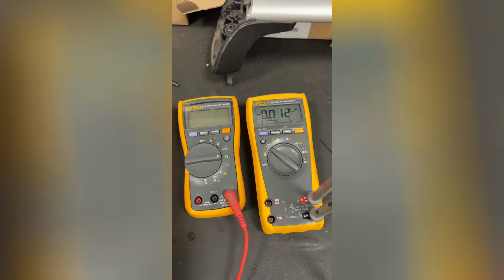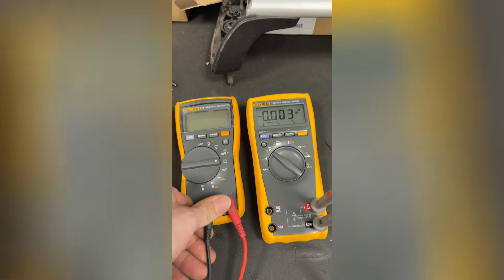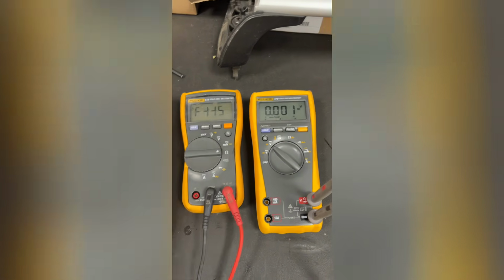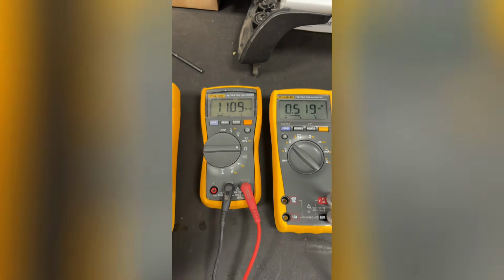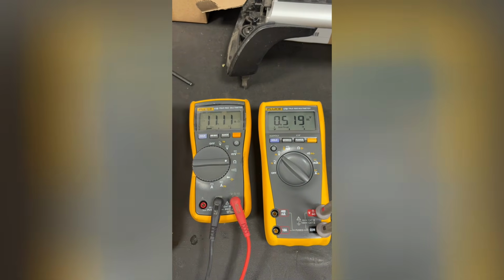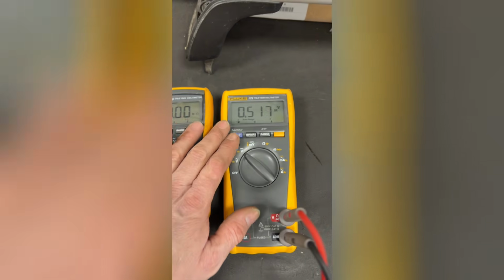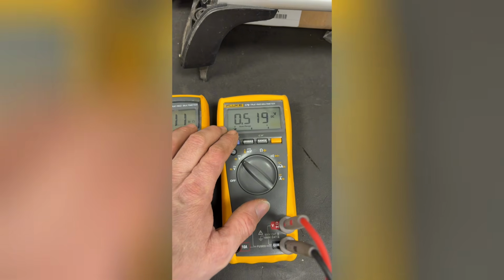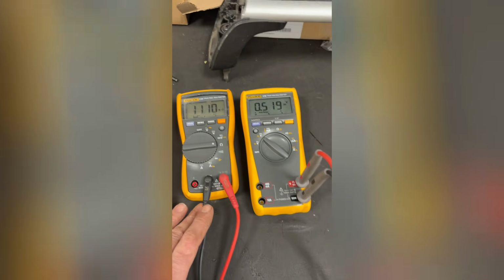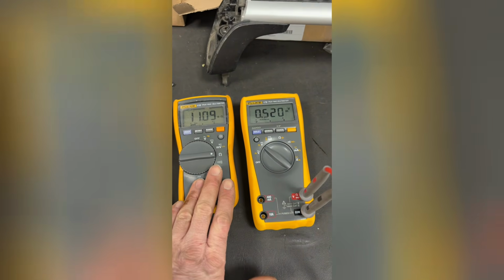We're going to go into the red port there, then the COM port here, and do a resistance measurement. Now with this one you don't need to press test, but straight away you can see this meter is returning a value of 11 megaohms. This meter essentially is putting out half a volt. So to check resistance on a set of wires, this is ideal for low voltage stuff.